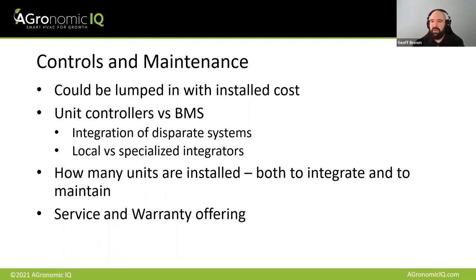In terms of the controls and maintenance piece, the more individual units you have in your facility, the more redundancy you have, but the more points of failure you have, and the more things that you need to either fix, clean or replace. I'm talking about filters, for instance. If you've got 30 small dehumidifiers serving a space and you have to change those filters between every cycle, there's a cost associated with that. There's a cost associated with putting a maintenance guy on a ladder and having him actually change those filters. And then if you have a contamination event, or if you're in a jurisdiction requiring it, needing to clean those units on or between every cycle, it again represents a pretty significant cost, or the opportunity to have a pretty significant cost. So all of these things factor into your overall cost of ownership.